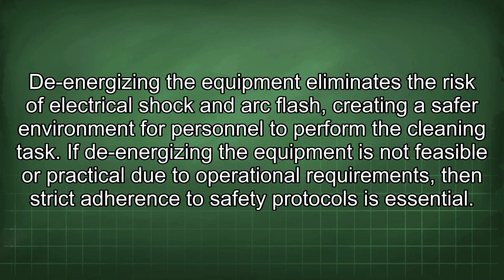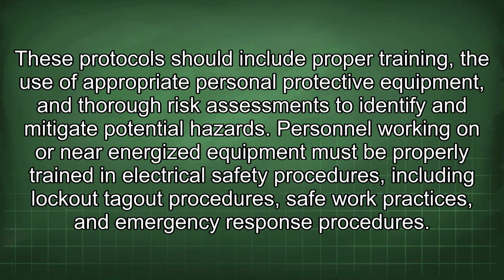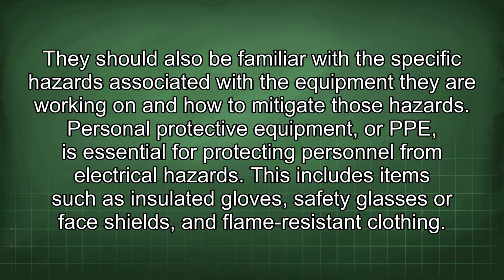If de-energizing the equipment is not feasible or practical due to operational requirements, then strict adherence to safety protocols is essential. These protocols should include proper training, the use of appropriate personal protective equipment, and thorough risk assessments to identify and mitigate potential hazards. Personnel working on or near energized equipment must be properly trained in electrical safety procedures, including lockout-tagout procedures, safe work practices, and emergency response procedures.